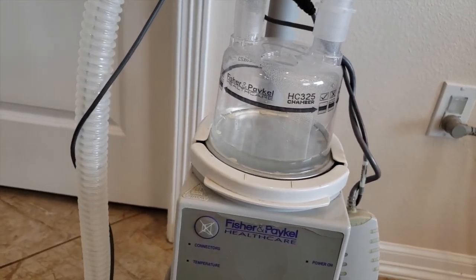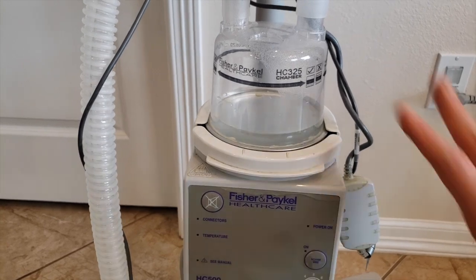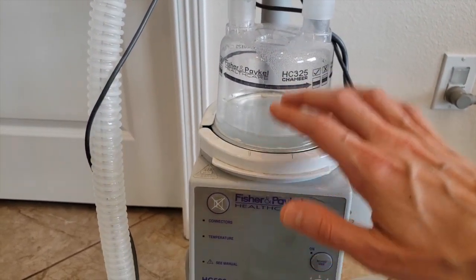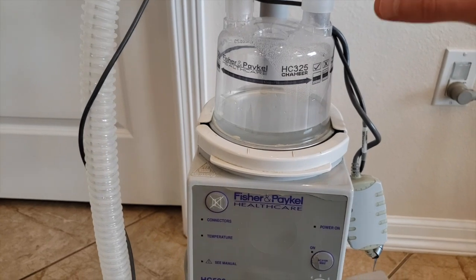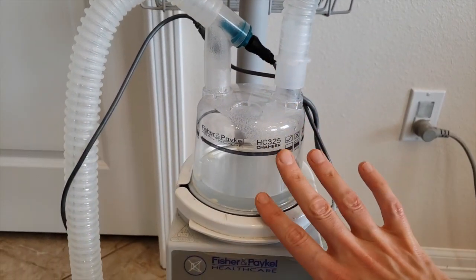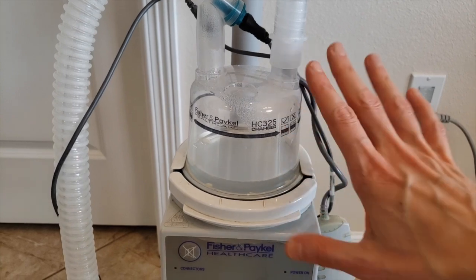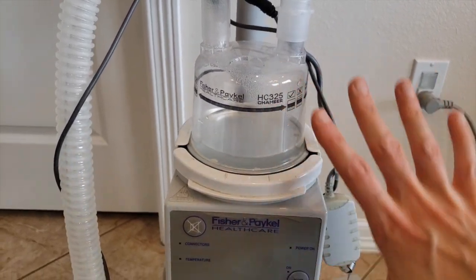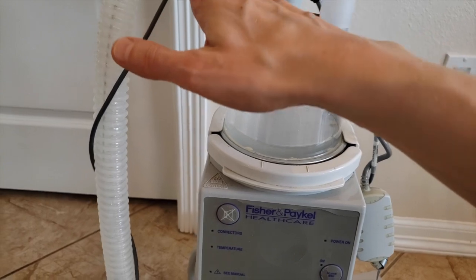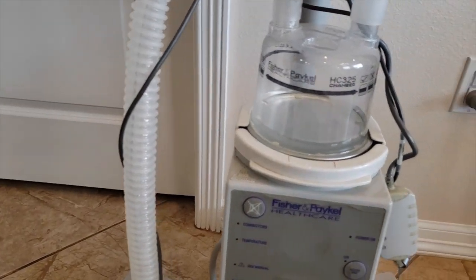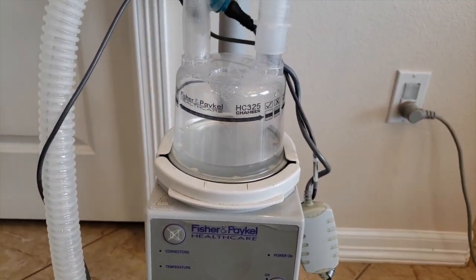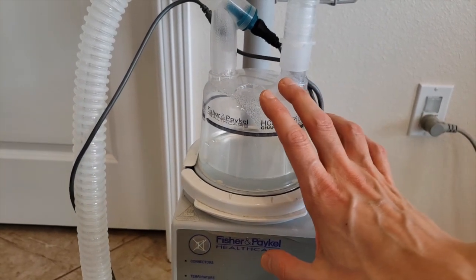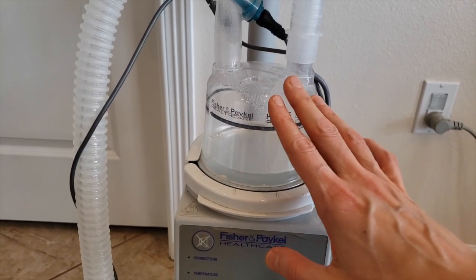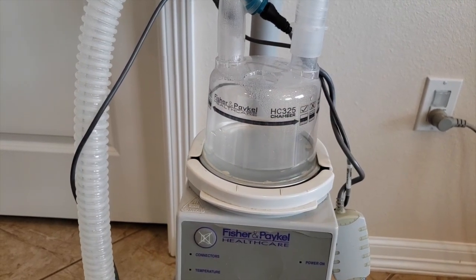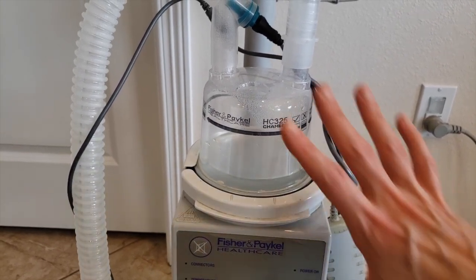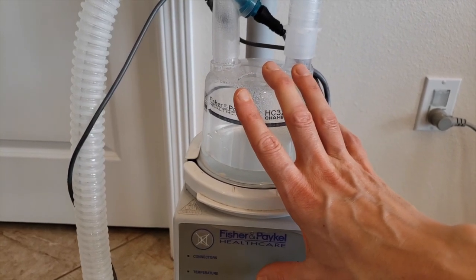I'm going to quick switch this over one moment. So one thing to note, this is called the water chamber. This is where you put water inside as the air is coming down here. It is just regular room air, which is usually pretty dry. It comes, it passes over this water, it picks up moisture, and then it's going to go through this tube and then get delivered to the lungs. And now you think, why would I want water in my air that I'm inhaling? The reason is room air is very dry and it will dehydrate the lungs. So this water chamber is essential to have.